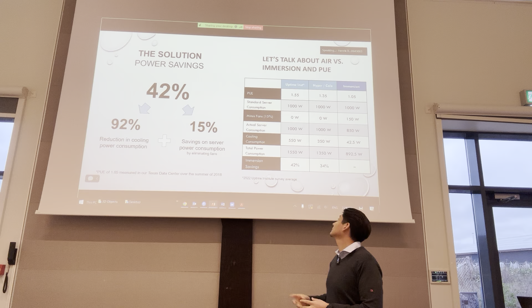The capex, a lot of it depends. Your power infrastructure gets reduced because you're not wasting all that capacity. Your generators or UPSs, no more need to account for the fans, stuff like that. No CRACs, no air handlers, no raised flooring. You really simplify an installation, and that can save you a lot of dollars at the beginning.